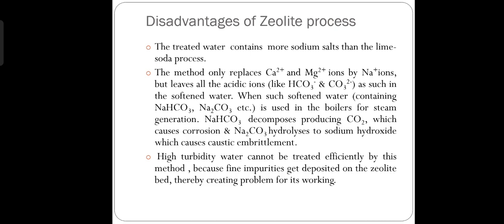Now coming to the disadvantages of the zeolite process. The treated water contains more sodium salts than the lime soda process. If we compare with the lime soda process, it contains more sodium salts. The method only replaces calcium and magnesium ions by sodium ions, but leaves all the acidic ions like bicarbonate ions, HCO3 minus, and carbonate ions as such in the softened water. They are present as they are.